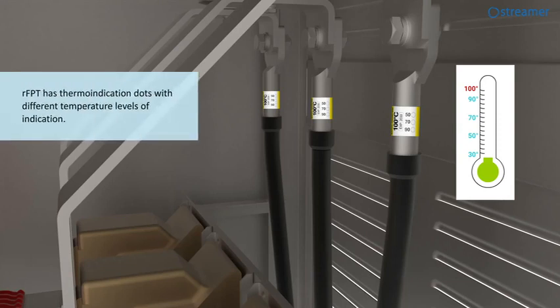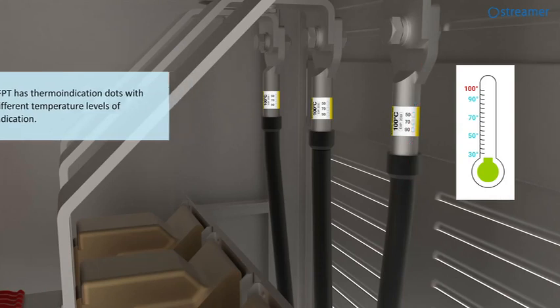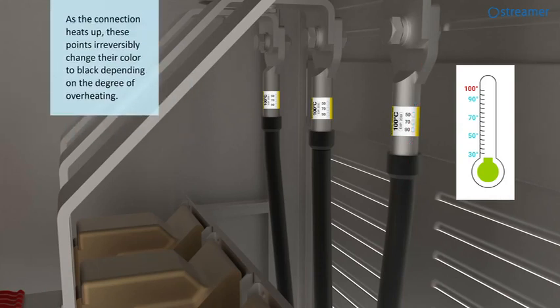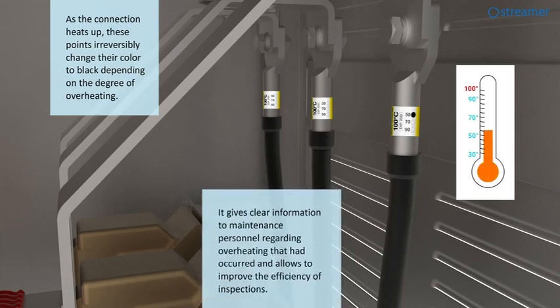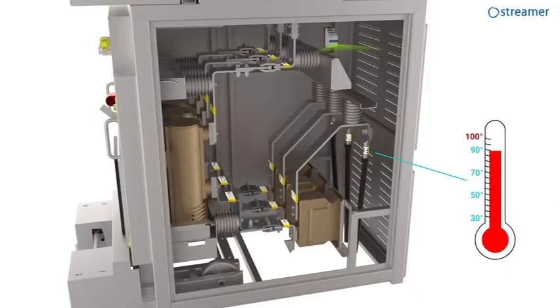rFPT has thermoindication dots with different temperature levels of indication. As the connection heats up, these points irreversibly change their color to black depending on the degree of overheating. It gives clear information to maintenance personnel regarding overheating that had occurred and allows to improve the efficiency of inspections.